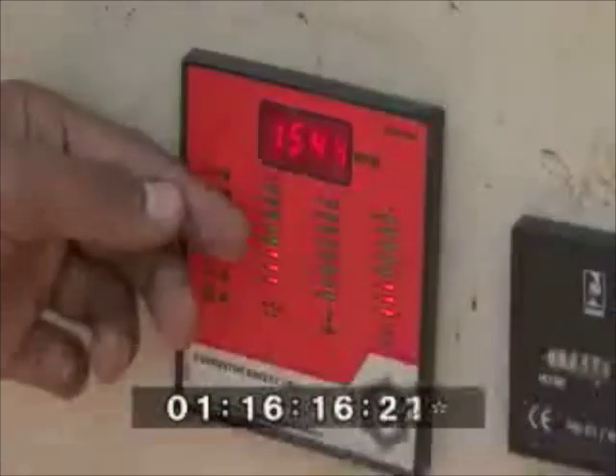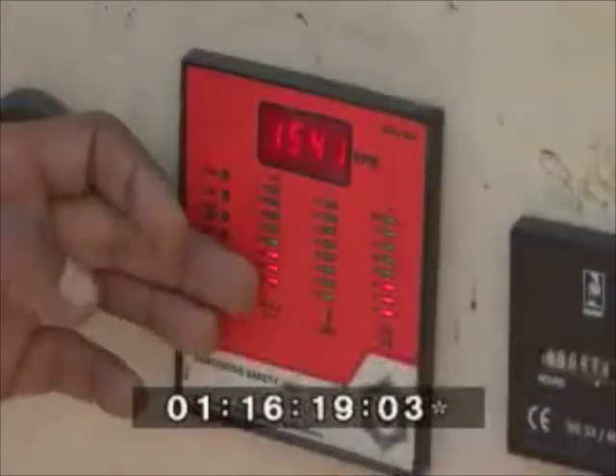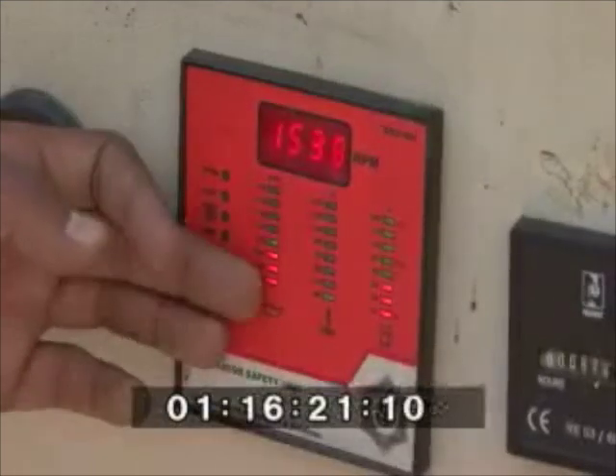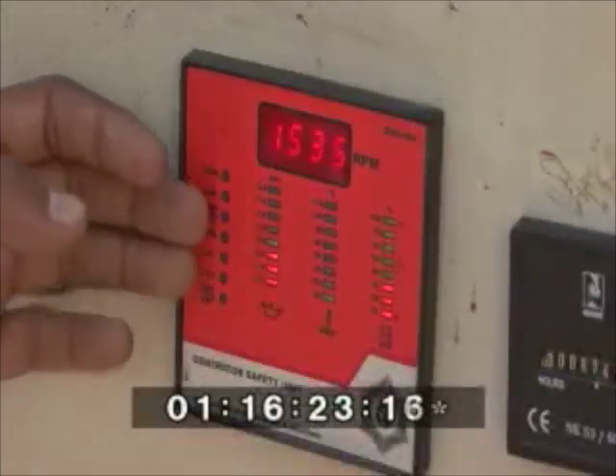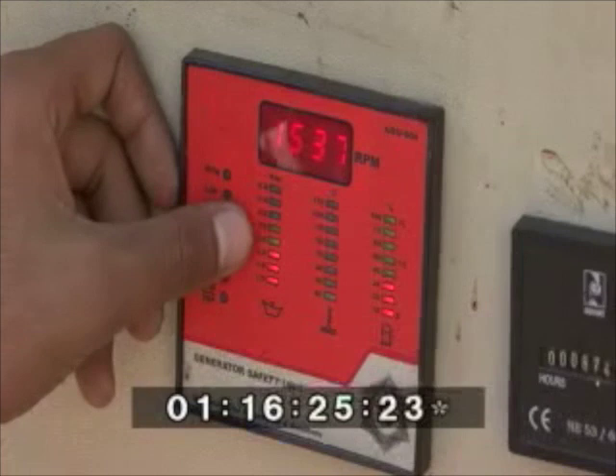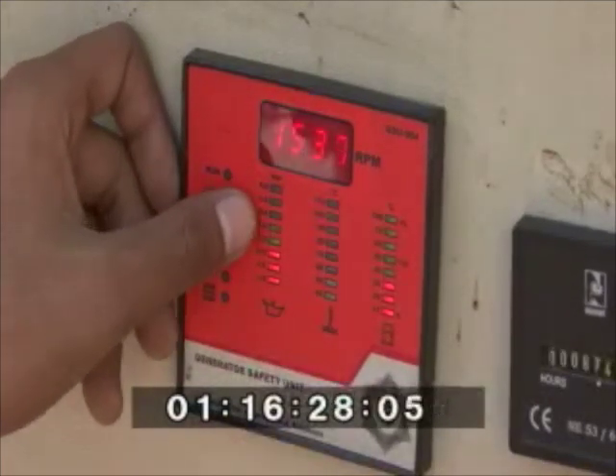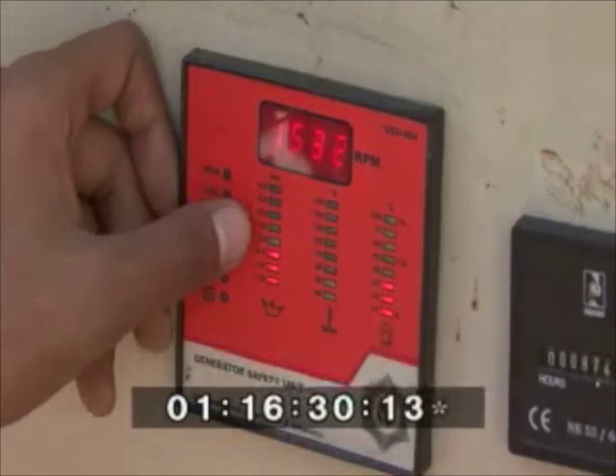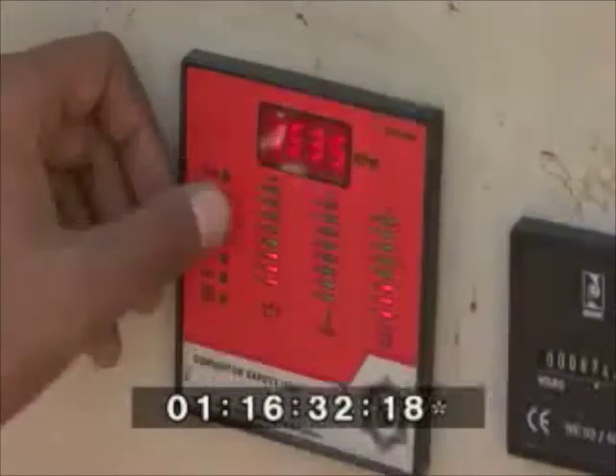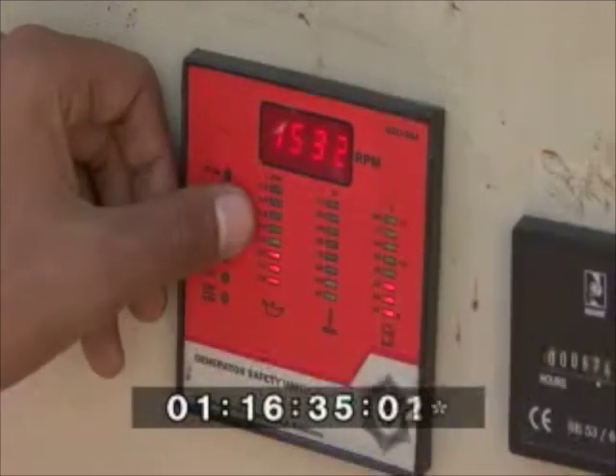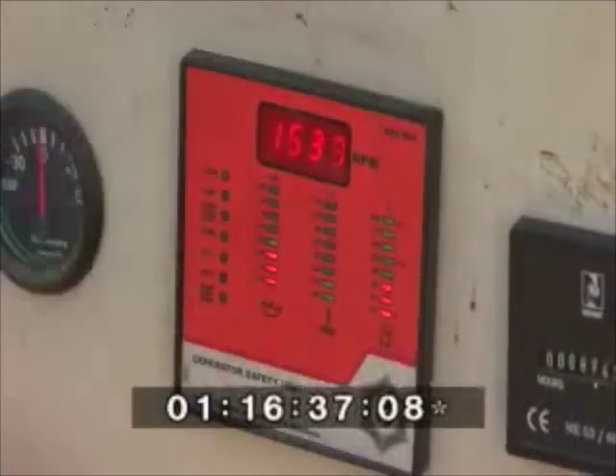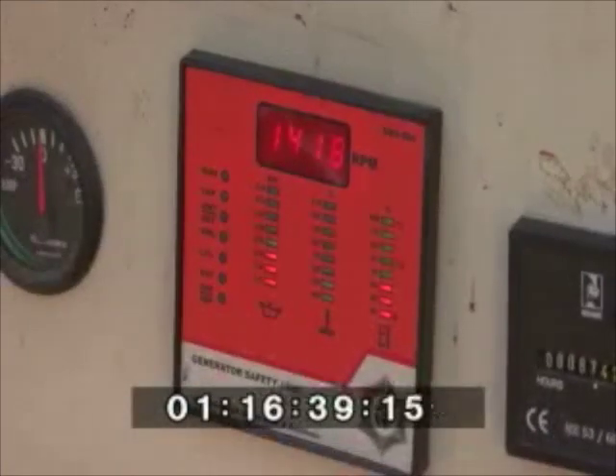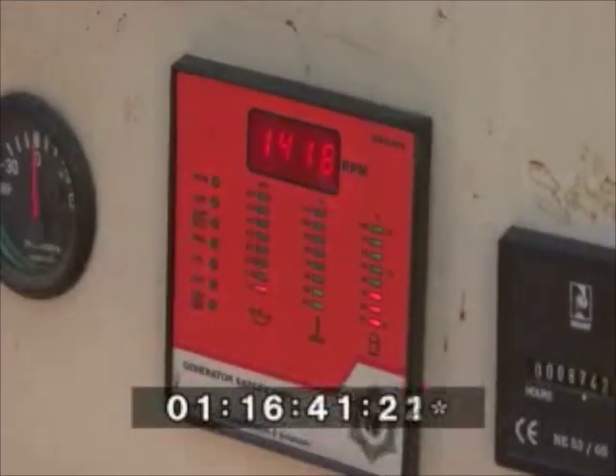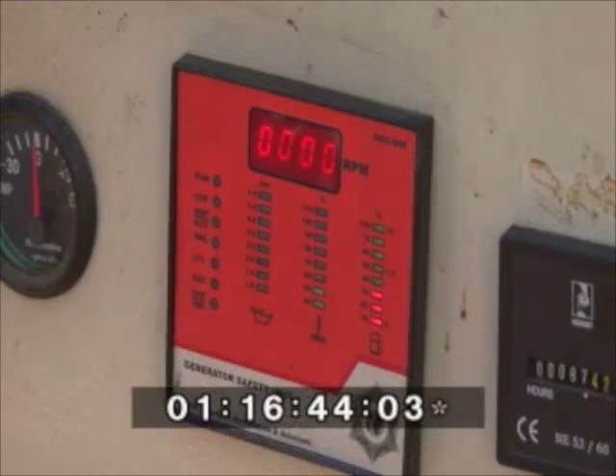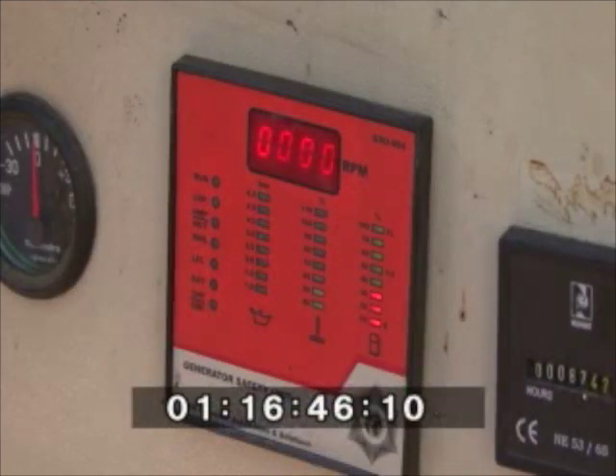The first bar meter in the left shows the DG lube oil pressure. The level should remain between 3 to 4. In case it drops below and gets near the red indicators, we need to check the DG lubricant. Now you can see that as soon as we shut the DG off, the LLOP bar comes down.